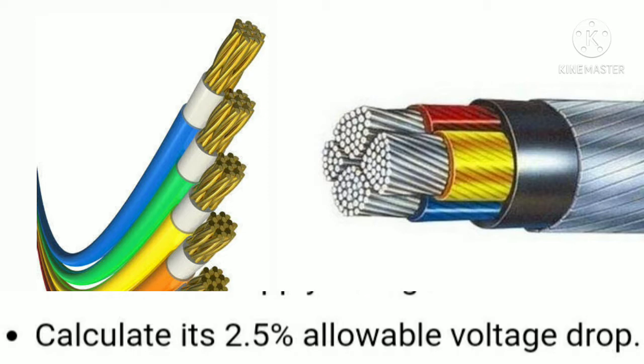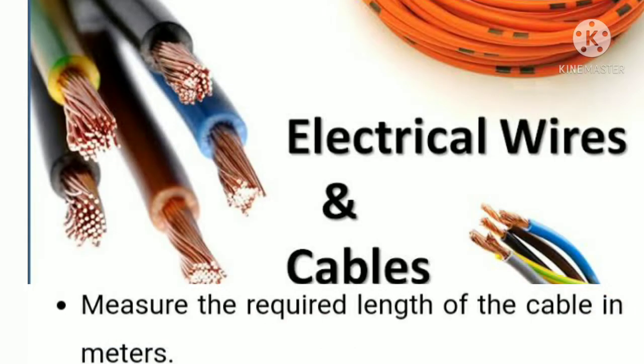The second point is to calculate the allowable voltage drop, which is 2.5 percent. If the voltage drop is higher than 2.5 percent, the cable size is not sufficient. It is allowed to have a voltage drop of 2.5 percent or less.